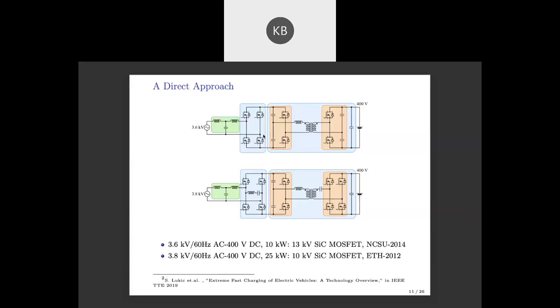The second problem is if you switch this at 10 or 20 kilohertz, switching 10 kV or 7 kV at that frequency, think about the DV/DT and how much EMI this is going to generate. That's also a big challenge. Another problem is you need capacitors which can withstand this high medium voltage.